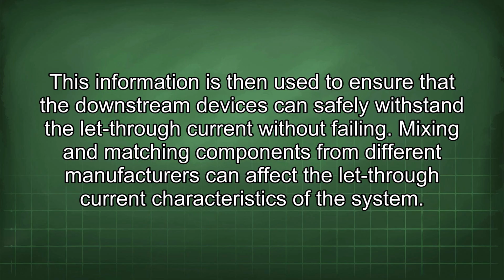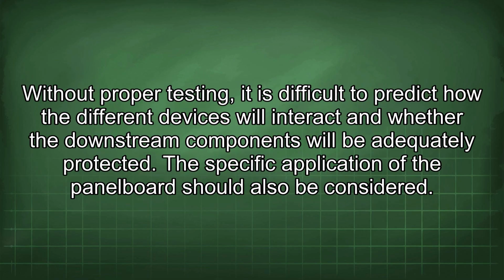This information is then used to ensure that the downstream devices can safely withstand the let-through current without failing. Mixing and matching components from different manufacturers can affect the let-through current characteristics of the system. Without proper testing, it is difficult to predict how the different devices will interact and whether the downstream components will be adequately protected. The specific application of the panelboard should also be considered.